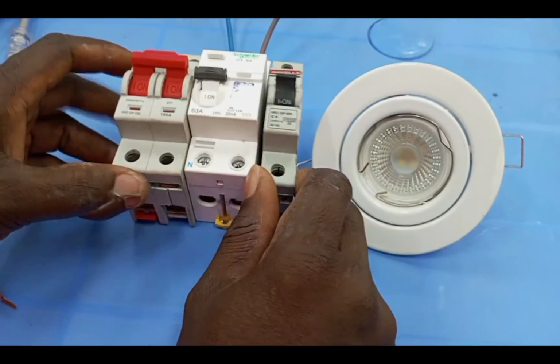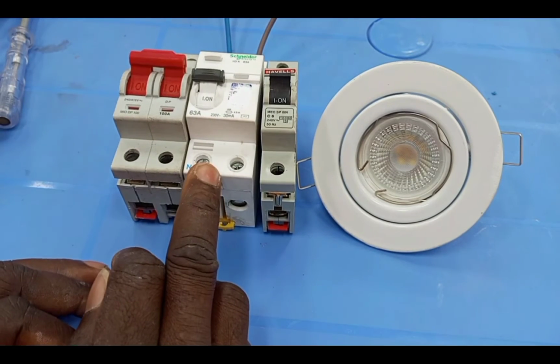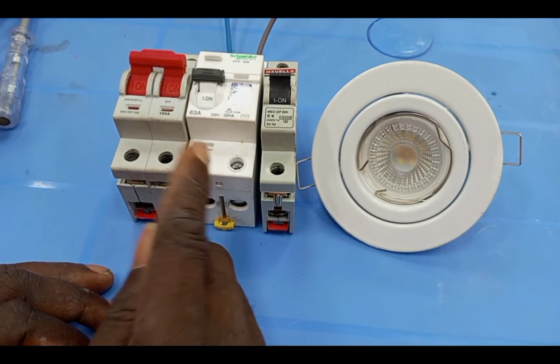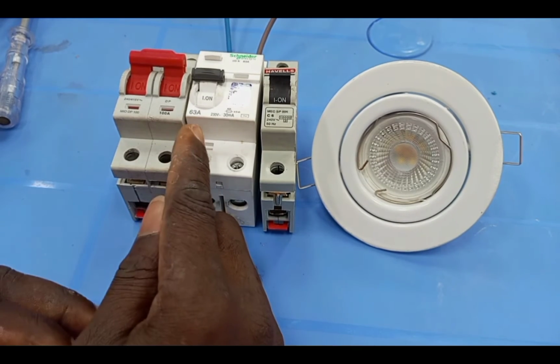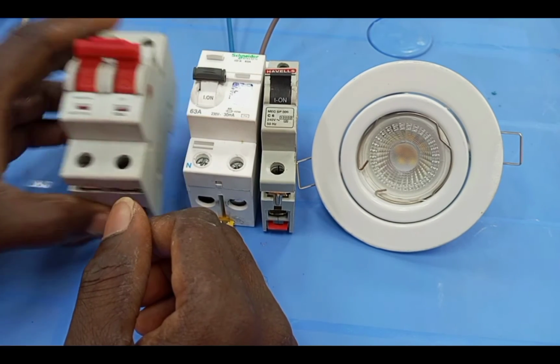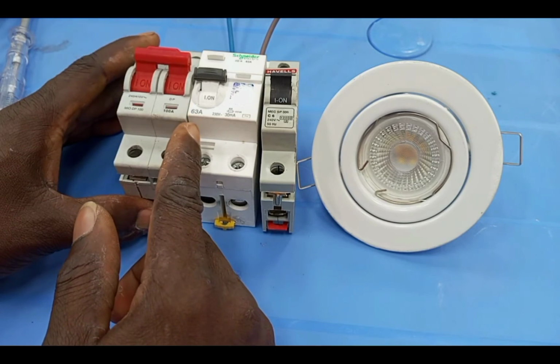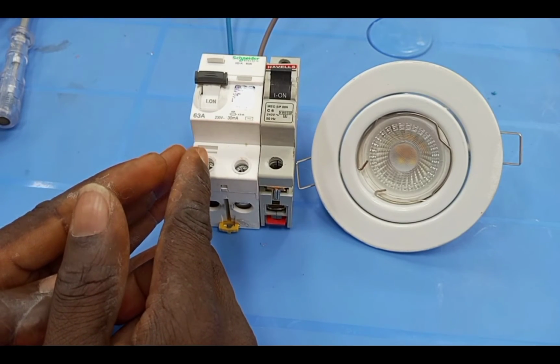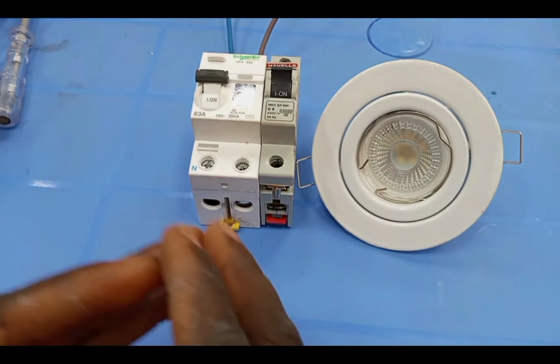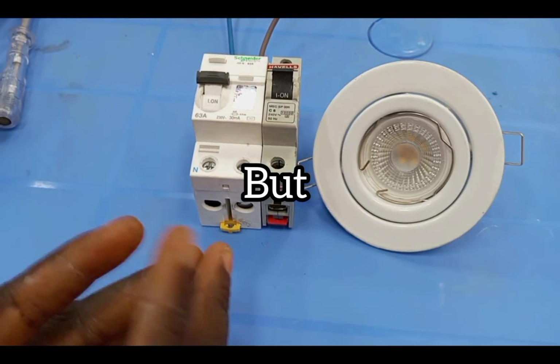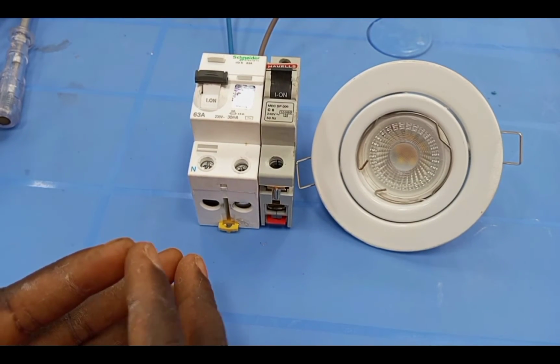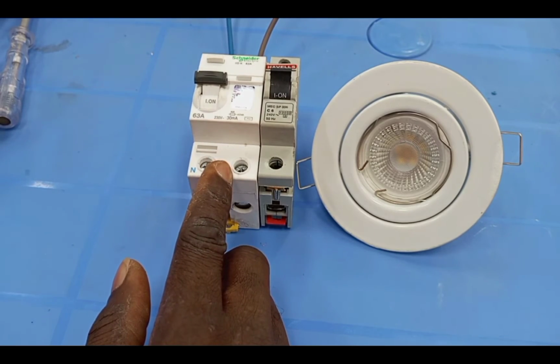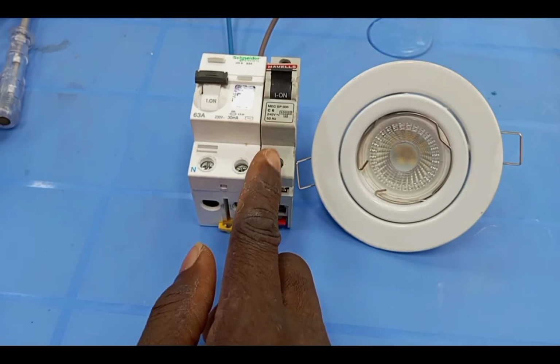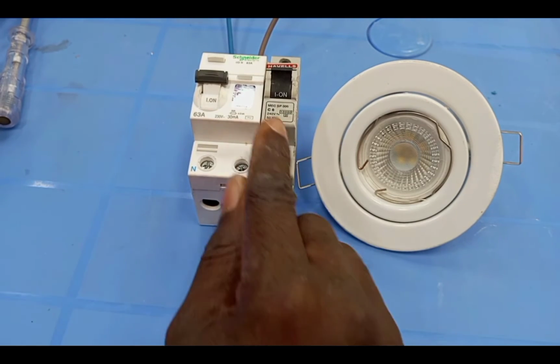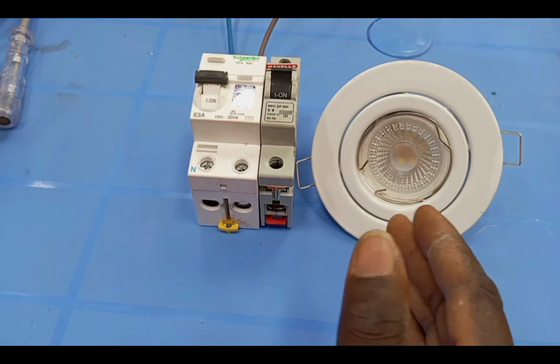All right. So assuming you want to use this RCCB to protect the whole wiring, then it means that the total load should not be more than 63 amps. And then there must also be a miniature circuit breaker of 63 amps to go with this one. Now, because this is 63 amps, we can use this one to protect this lamp and another load. But each of the loads that you will be connecting to this RCCB must have its own breaker protecting it. For instance, this 6 amp breaker should be connected to my lighting circuit.